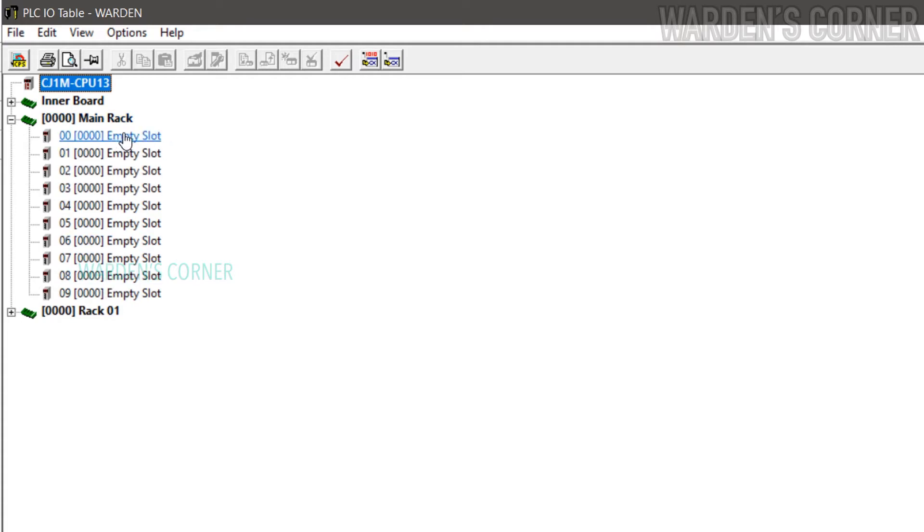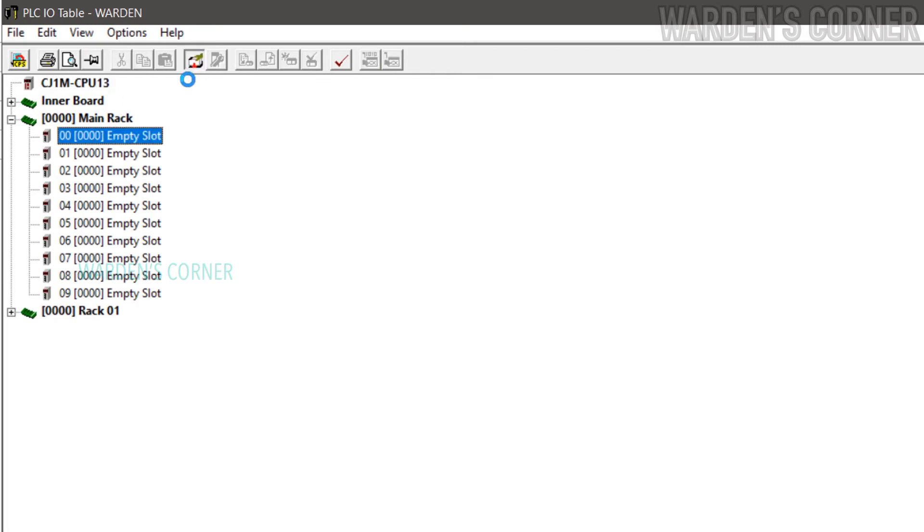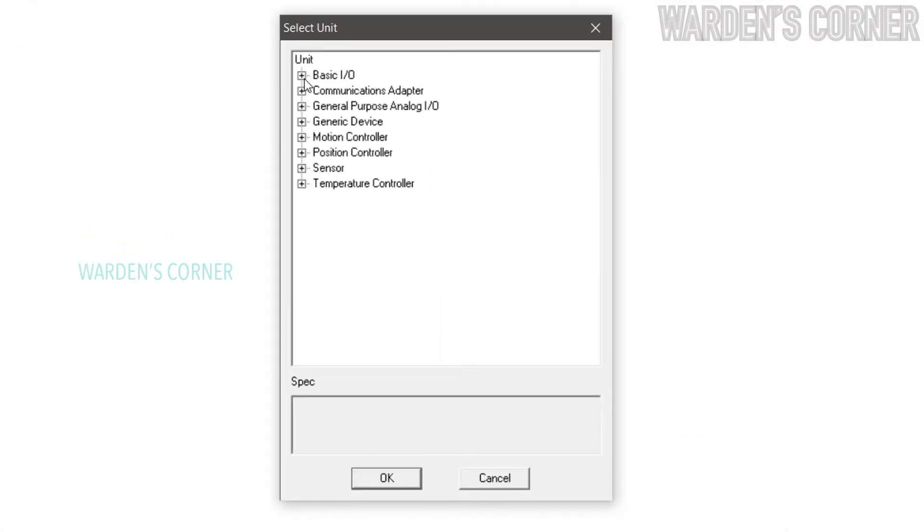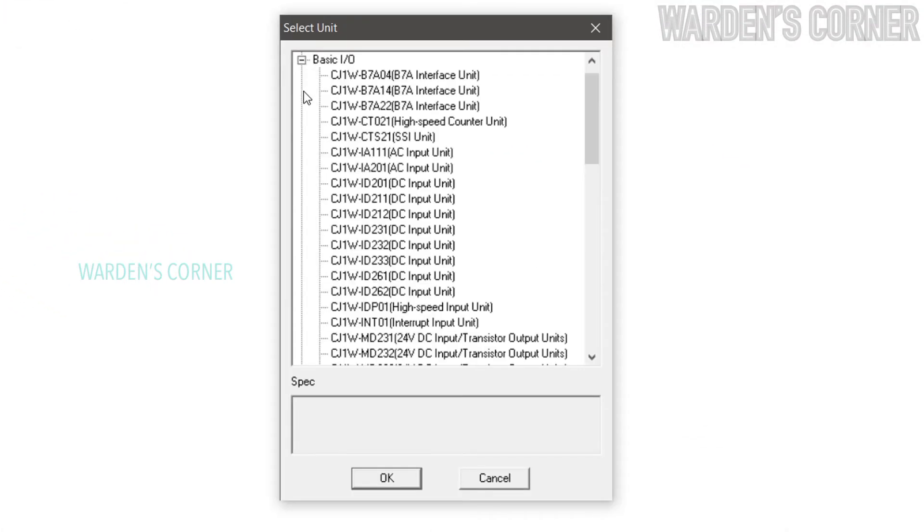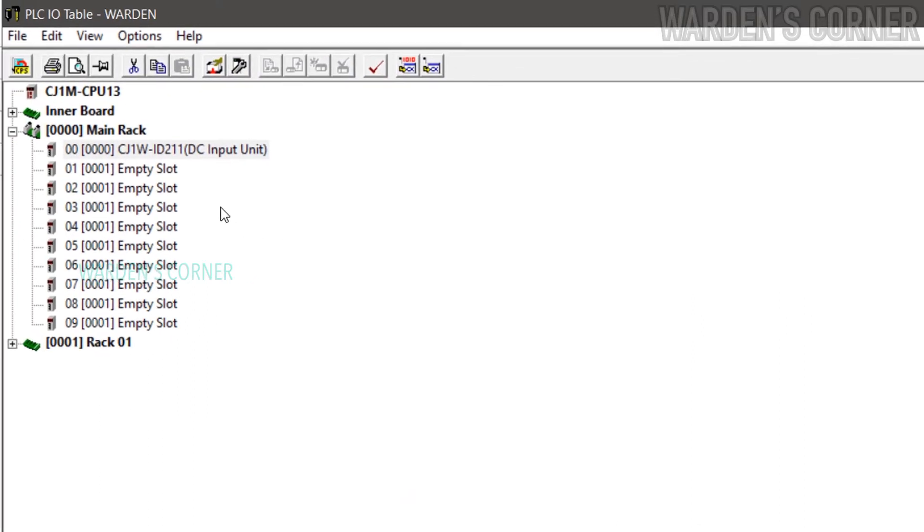In slot 00, it is where the input card will be designated. Click Add Unit icon, click Basic I/O, and select CJ1W-ID211, DC input unit. And click OK. As you can see, the input card has been added to slot 00.